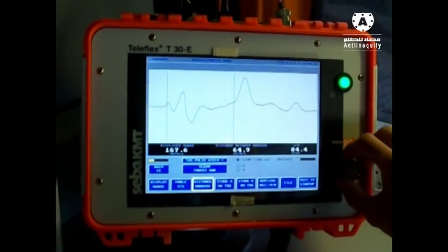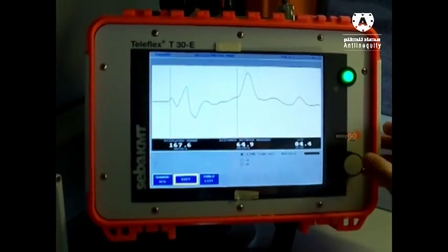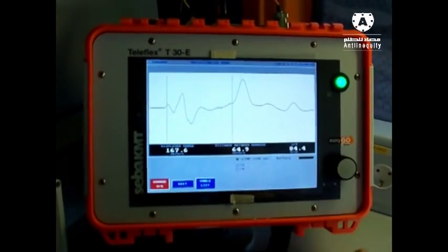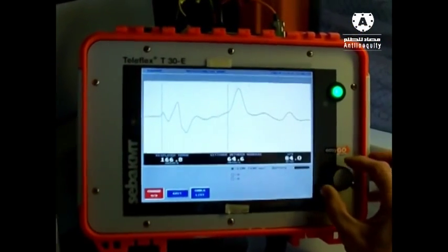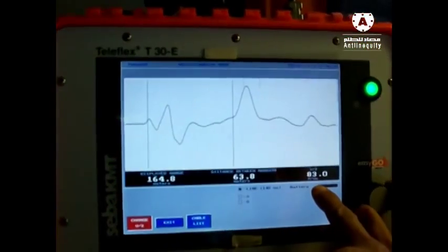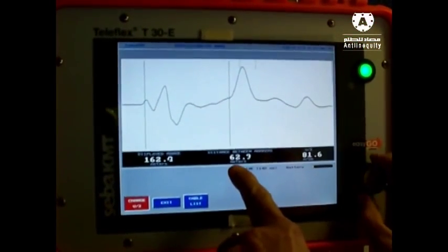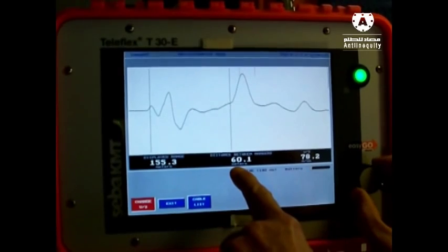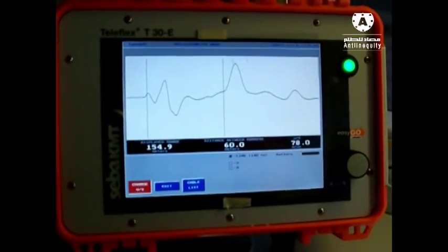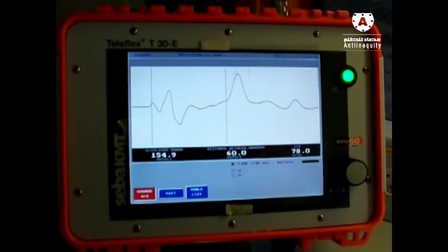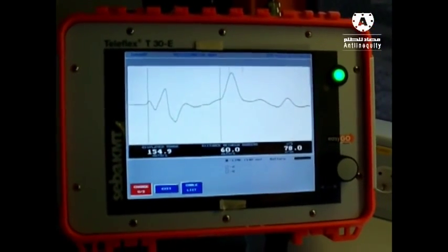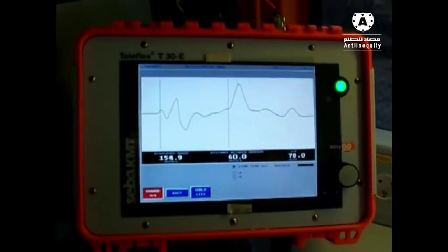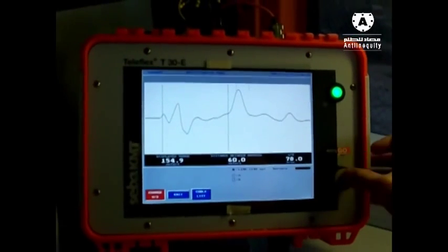Let's go back. We adjust now the velocity by hand. If our real length is only 60 meters, you see we have to decrease here the velocity so that we reach the real cable length at this point. That means the real cable length of our test band is in this special case 60 meters. If your cable is much longer than 60 meters, about 80 meters, you must do the same steps, but then you have to increase to reach the real value. Okay?